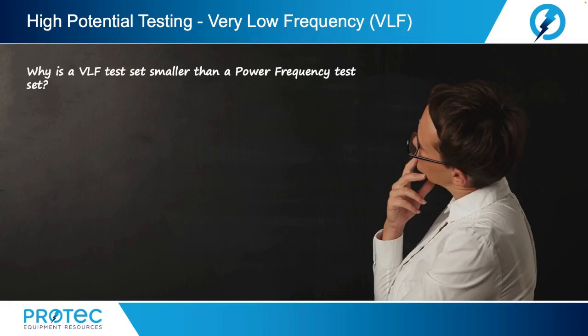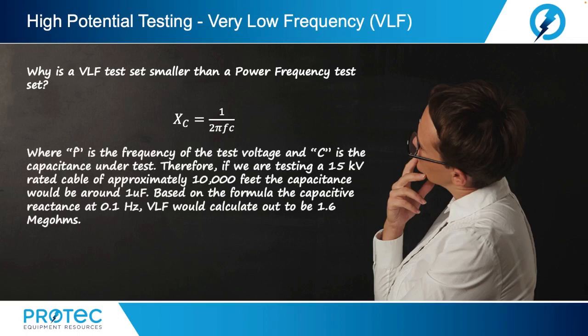So, why is VLF or very low frequency test sets smaller than power frequency test sets? Well, again, we have to go back to capacitive reactance equals 1 divided by 2 pi Fc, where once again, F is the frequency of the test voltage and C is the capacitance of the cable under test. So, if we are testing a 15 kV rated cable of approximately 10,000 feet, the capacitance would be around 1 microfarad. Based on the formula, the capacitive reactance at 0.1 Hz test frequency would calculate out to be 1.6 megohms, as we see here.